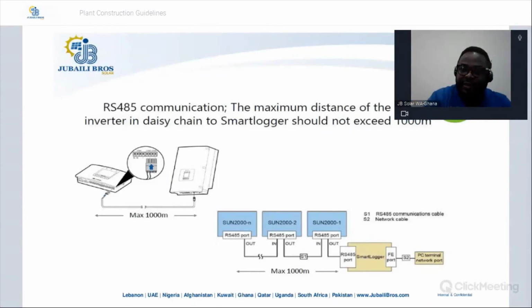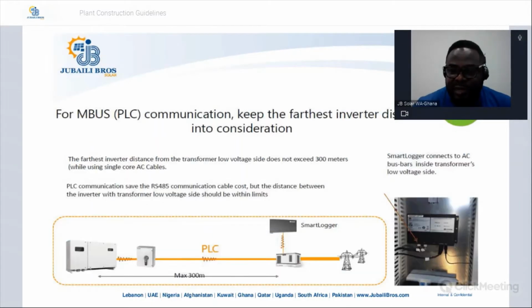900, 800, 700, 500. The closer, the better, of course. The closer, the better, the faster the communication. The furthermost, then we are beginning to lose some communication power. And if it goes beyond 1 kilometer, normally you begin to face communication challenges. So this is the biggest advice. So here you see inverter 1, 2, 3, up to whatever inverter. For this last inverter in the system, the distance to the smart logger should not be more than 1,000 meters. Please, let us take note of it, especially for utility scale or big C&I project developers. Let's put this at the back of our minds.